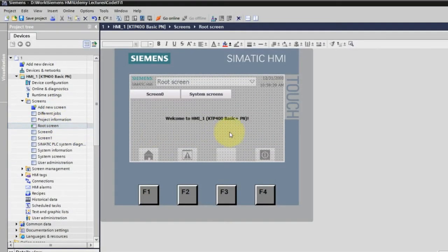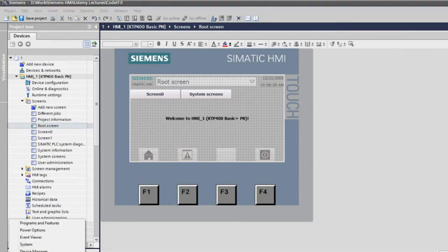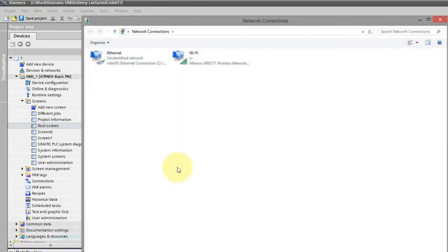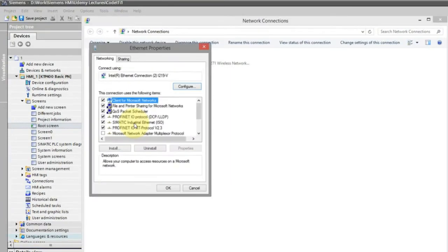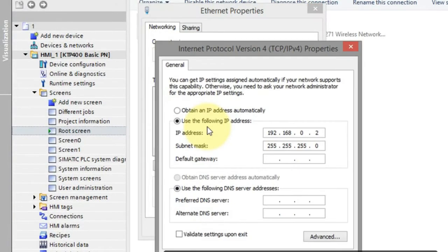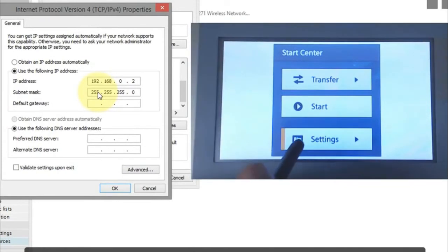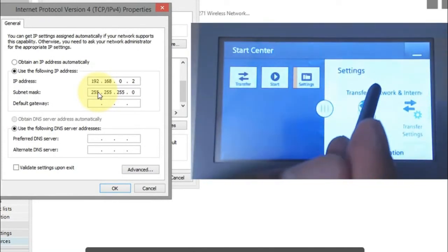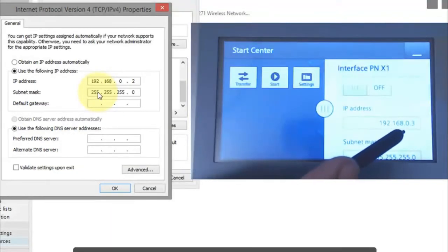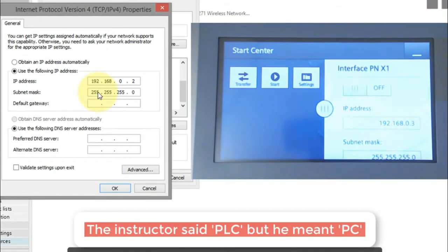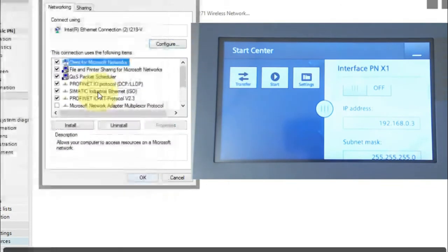Now the project is ready to transfer to the HMI. First, we need to verify IP addresses. Go to Control Panel and open Network Connections, then check the Ethernet adapter's IP address — it is 192.168.0.2. This is one less than the HMI's IP address of 192.168.0.3. You can verify on the HMI by going to Settings, then Network Interface, which confirms 192.168.0.3. This configuration is correct.